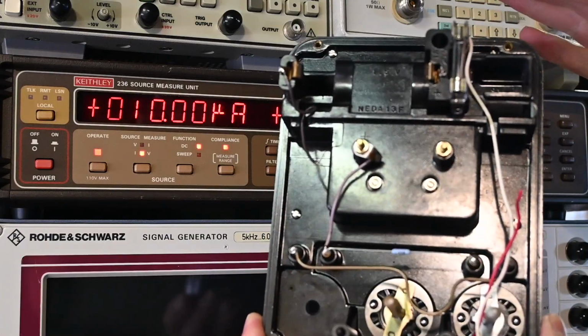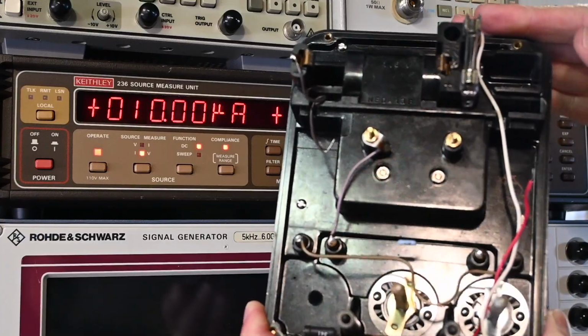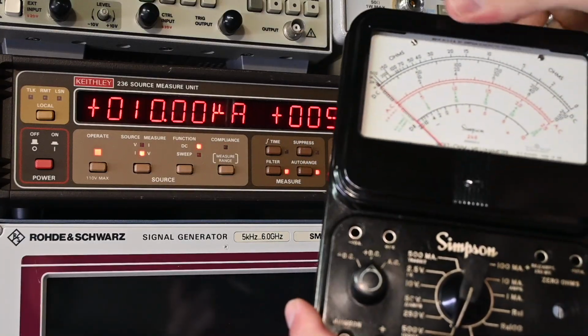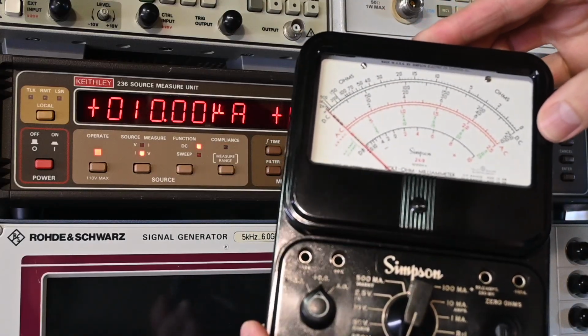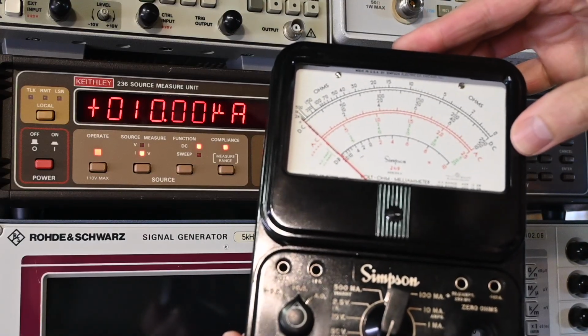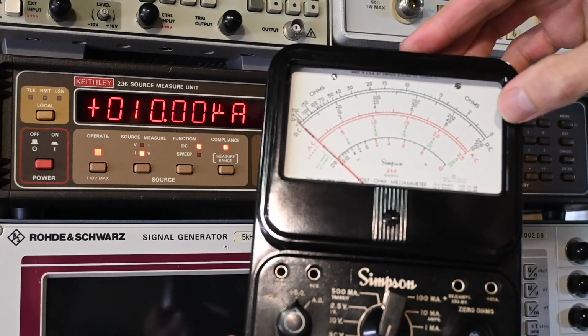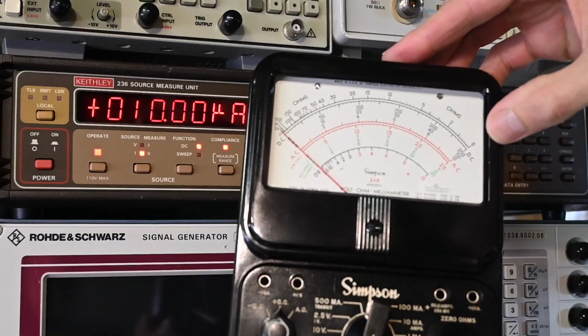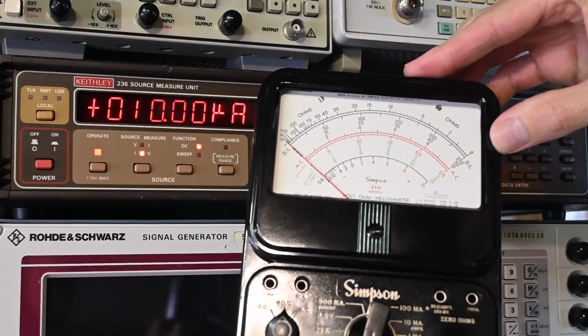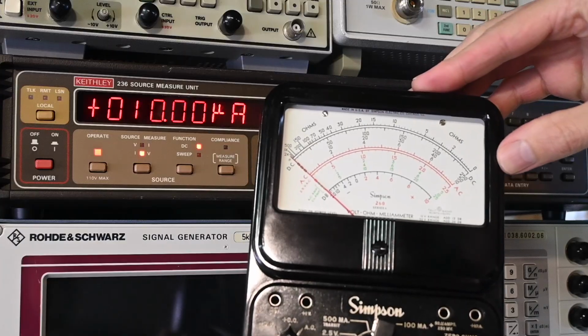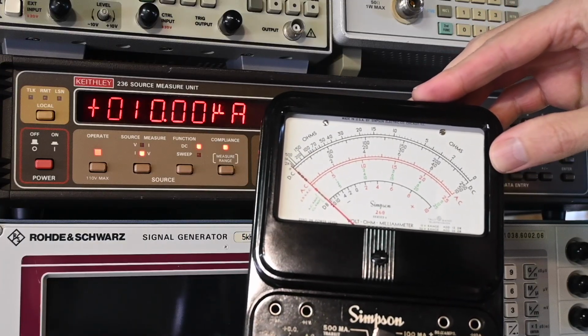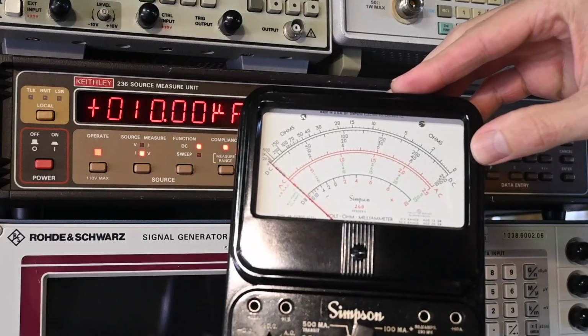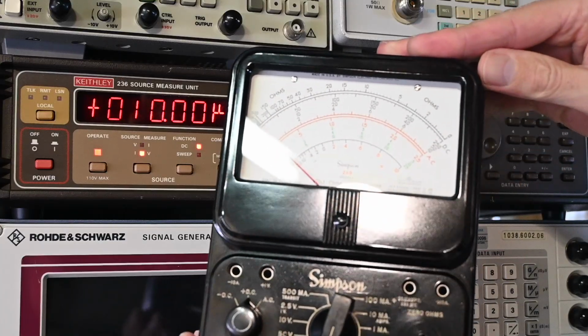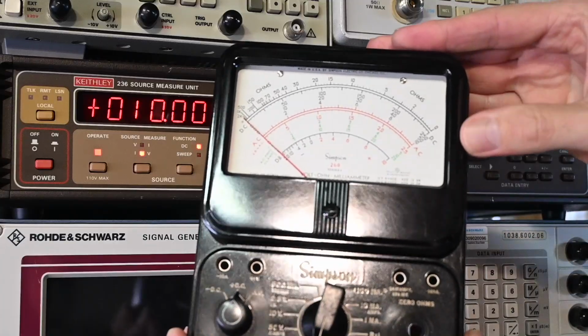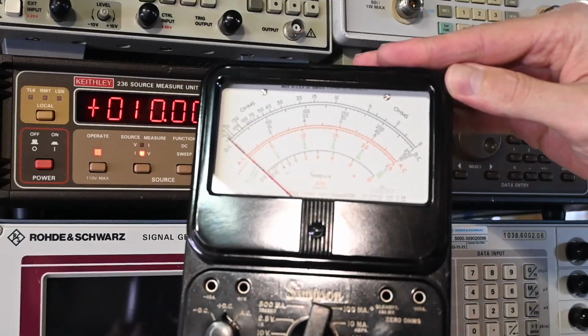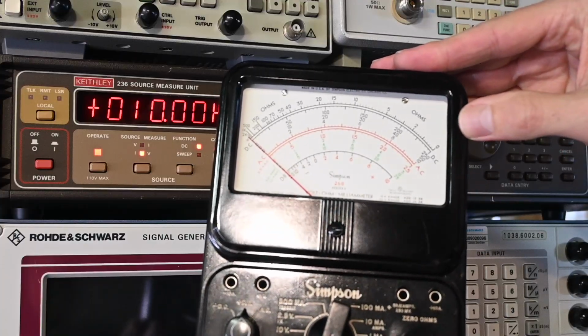And with this check and this test, you have to be very, very careful, because this meter has a full scale deflection all the way over to the right-hand side of about 50 microamps. But it's a little bit less than 50 microamps when the needle is pointing all the way to the end of the actual dial. And we want to see exactly what that is. It's not really needed for the actual calibration, but I'm just curious to see what the measurement is. It should be about 48 microamps, maybe just a little bit under that, but probably around that amount. I just want to make sure that that's actually how this meter is behaving and working. Okay, so again, 50 microamps is full scale off the end, but a little bit less than that is what we expect to see for the dial itself.